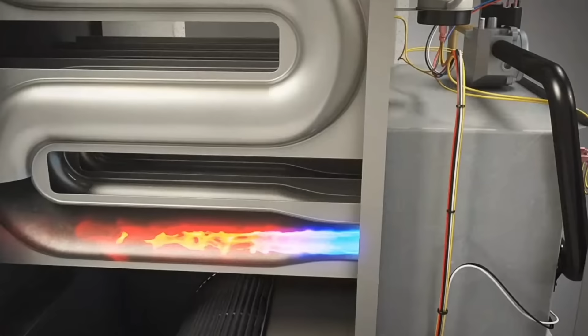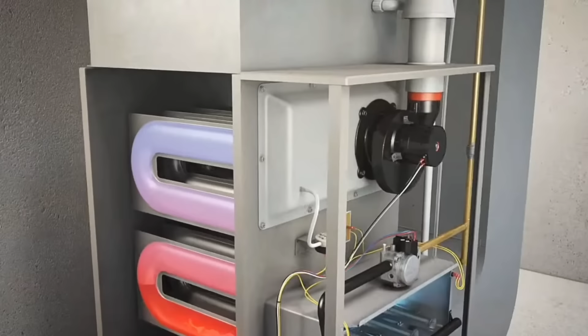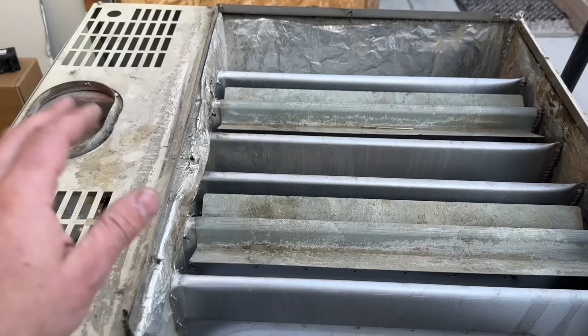Now, if you haven't seen what a heat exchanger looks like, basically that flame in there is traveling through and the inducer is actually pulling that flame out, and then it goes out this way. So in reality, if you do have a crack in your heat exchanger, the air that is blowing through here is going to get into that hole, not vice versa. The carbon monoxide is not going to come out typically. That's very uncommon. More so, the oxygen, the air that's being pushed through here, is going to go into the heat exchanger, and that's going to disrupt the flame in there. So let's go ahead and shut down our furnace and we'll get into our test.